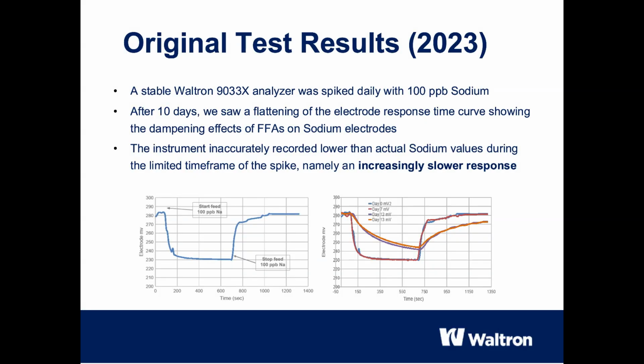Our initial investigations in 2023 already gave us cause for concern. In this test, we ran a stable Waltron 9033X sodium analyzer continuously with a sample, adding a daily spike of 100 ppb sodium to simulate a contamination event. As you can see in the graphs, the electrode response changed drastically over time. Initially, we see a rapid and significant response to the spike.